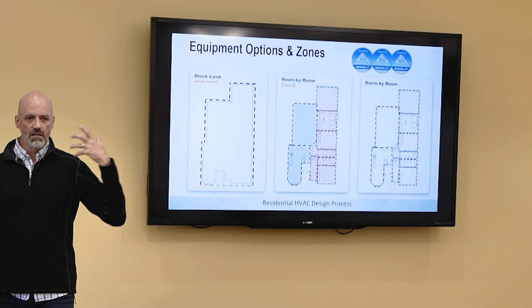Certainly in the multi-zone heat pump arena, for sure. There are tools out there from different manufacturers. Some of them are just spreadsheets. This one happens to be from Mitsubishi, and there are other manufacturers that do, like Daikin, I think, has something similar. LG has something similar. Carrier, I think, has something similar to this. And the goal is to lay out the system so you've got your outdoor, you've got your indoors, and then you've got your zone capacities, if you will, and then you check these numbers against your load calc, right?